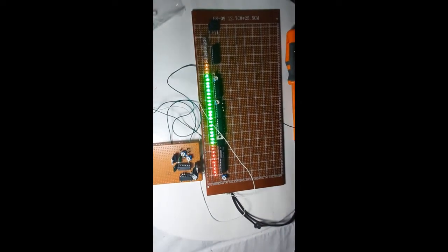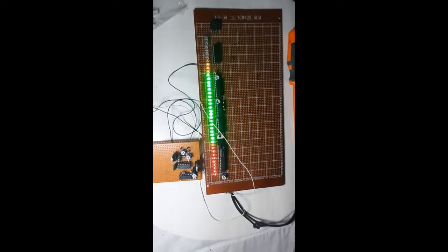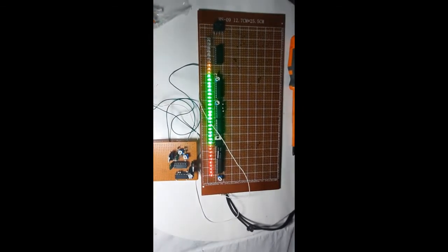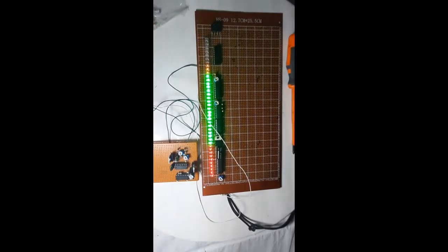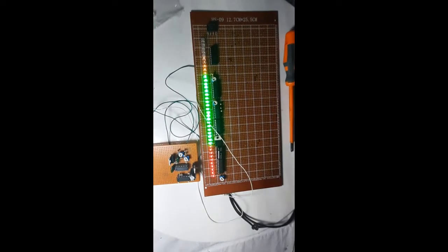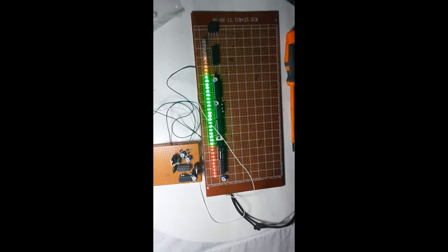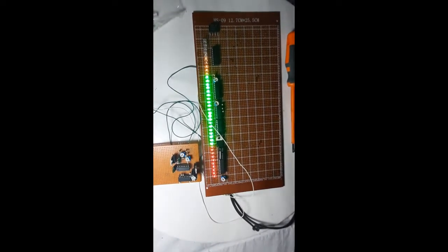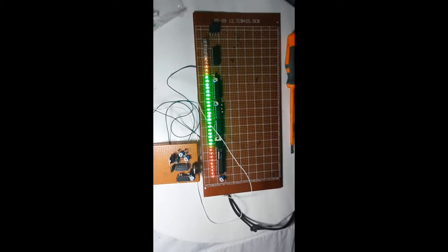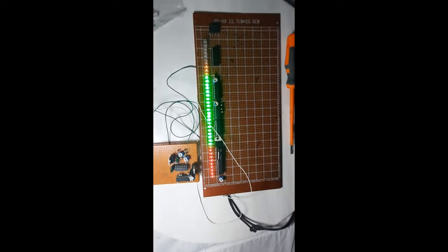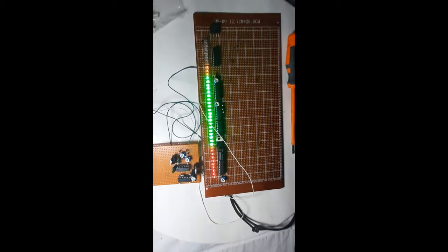Basically these are commonly used in marine applications for cranes, right? So we will see how this signal is taken and brought to the display unit or the control unit. Now this load cell generates a maximum of about 5 millivolt output. The 5 millivolt output is very low, extremely low. So we can't do anything with this output without properly amplifying it.